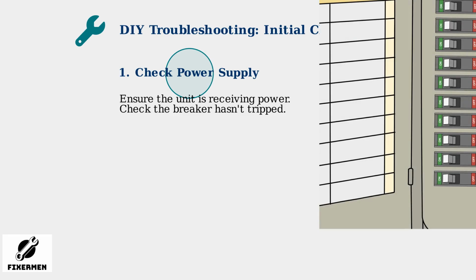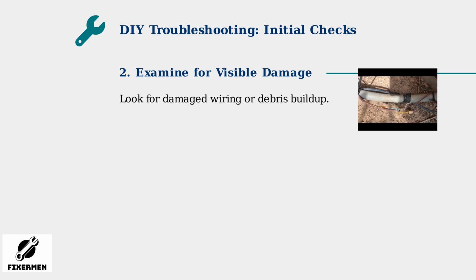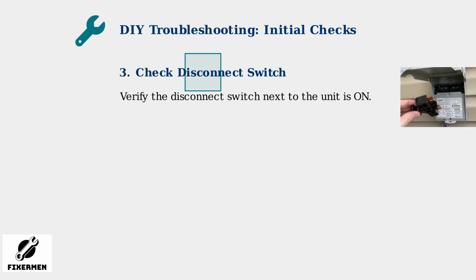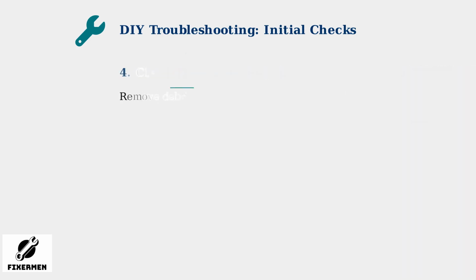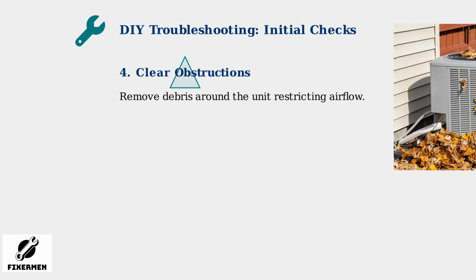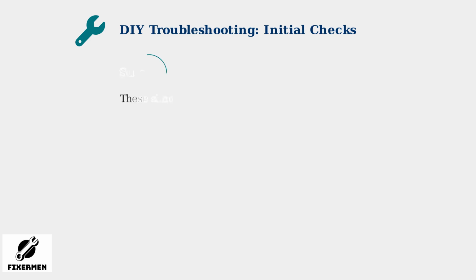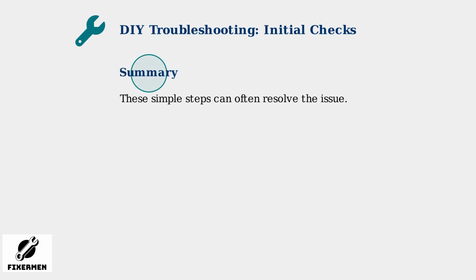Before calling a technician, perform these basic DIY checks. First, ensure the unit is receiving power. Check the breaker and ensure it hasn't tripped. Then, examine the unit for any visible damage, such as damaged wiring or debris buildup. Check that the disconnect switch next to the unit is in the on position. Clear any obstructions around the unit that may be restricting airflow. These simple steps can often resolve the issue without needing professional help.